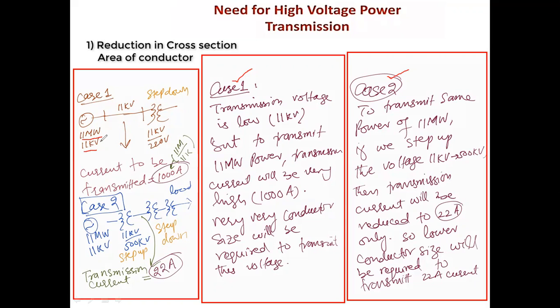So if we do not step up this 11 kV and directly transmit it to the consumer side, this is the consumer side, and this is the street transformer, having the rating of 11 kV to 220 volts. This is the only transformer in this case. So in order to transmit that much amount of power, we need to transmit 1000 amperes of current. P is equal to VI, I is equal to P by V. So 1000 ampere current is a huge amount of current.